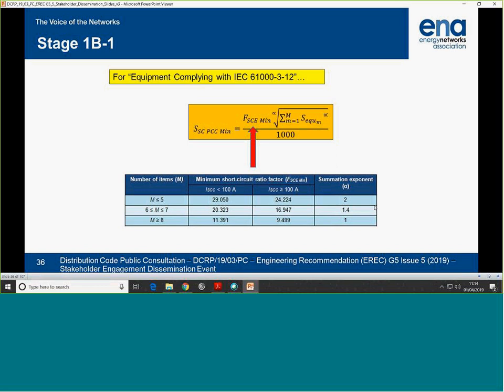So if you sum to 1, in the table below, and say ISCC, which is service current capacity, less than 100 amps. That would be whole current metered equipment for a DNO. Then the multiplier is 29.05. That's lower than 33 used in the other document I just talked about. So it's actually less conservative in that assumption. And you see all of these numbers are less than 33, indeed. And the way we got to that is by analysing it in a fuller way, taking account of THDI, X/R ratios, skin effect, and so on, which I'll come on to in a minute.